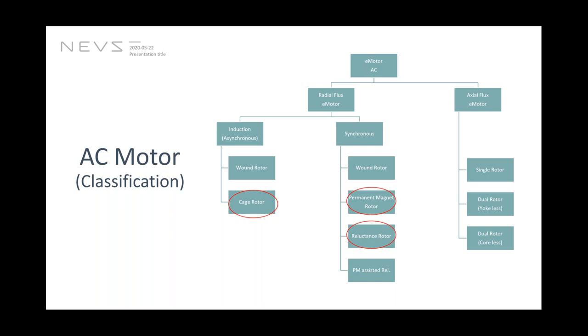And there are variants of induction motor which has wound rotor, cage rotor, and if you see the current trend, wound rotor probably is an extinct breed of induction motor. Right now, whenever you say induction motor, it's almost always a cage rotor. And then on the synchronous machine side, these are the machines in which the rotor rotates in sync with the rotating magnetic field in the stator. And again, there are different variants: permanent magnet rotor, reluctance rotor, permanent magnet assisted reluctance rotor. Out of all these machine variants, this is a very simplified classification. There are quite a lot of other motors as well. But out of this, the main points of interest for us in the HVAC application and other industrial application are the three that I have marked in the ovals: cage rotor, permanent magnet rotor, and reluctance rotor.